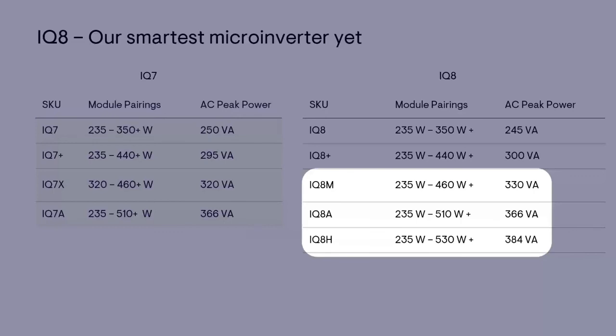Another question about compatibility of IQ8s and IQ7s: can you elaborate on the microgrid compatibility potential between IQ8 and IQ7 on one microgrid? Want to understand better the ability to use an existing IQ7 with the new IQ8 off-grid features. Within one microgrid, only IQ8s, or IQ7 and IQ6, can be installed - they can't be intermingled in the same microgrid. So if a customer has an IQ7 system and wants sunlight backup, meaning no batteries, they would have to replace their IQ7s with IQ8s. If they're willing to consider a battery, they should leave the IQ7s where they are and add more IQ7s to expand the system, coupled with a battery system. I'm not necessarily a proponent of replacing IQ7s with IQ8s, because the IQ7s work great with our batteries.